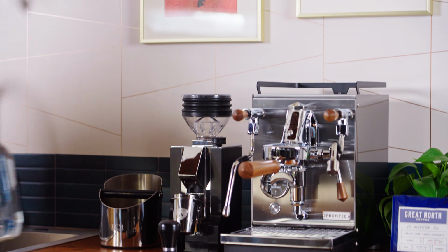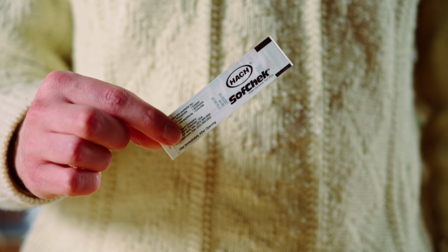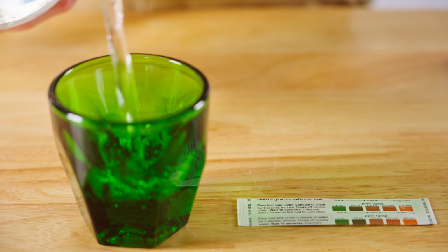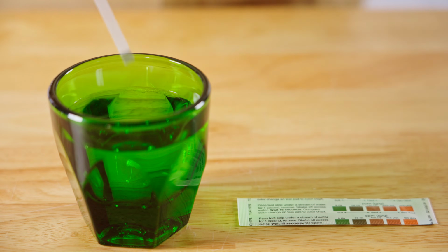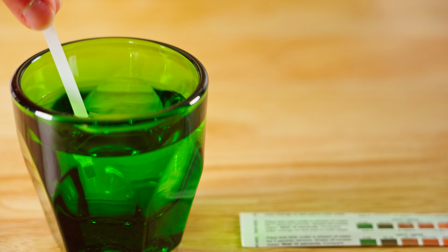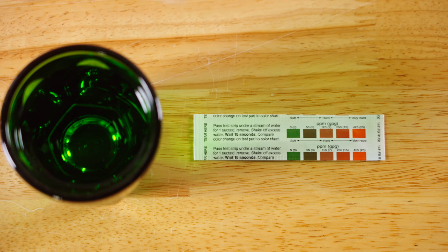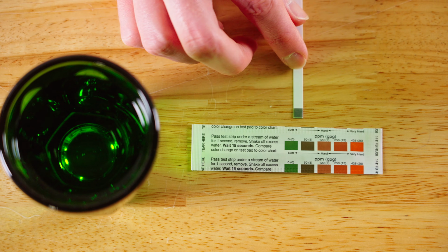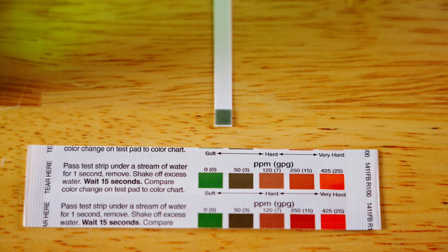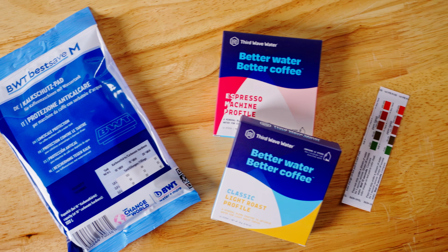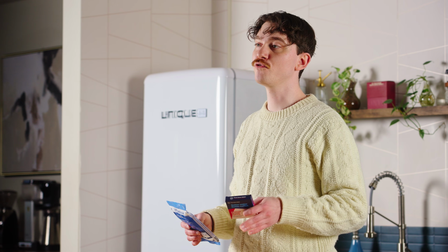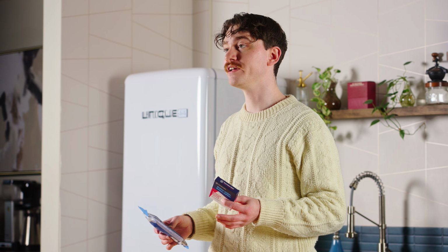Before introducing water to your machine, it's essential to test your water to ensure it's adequately soft to avoid scale buildup. Use the included water test strips to verify the hardness of your water. You're looking for a hardness around 50 parts per million. If it's too soft or too hard, we have multiple easy solutions to help you get it in the right range. Check the links below for more information on water quality, softening, and filtration.